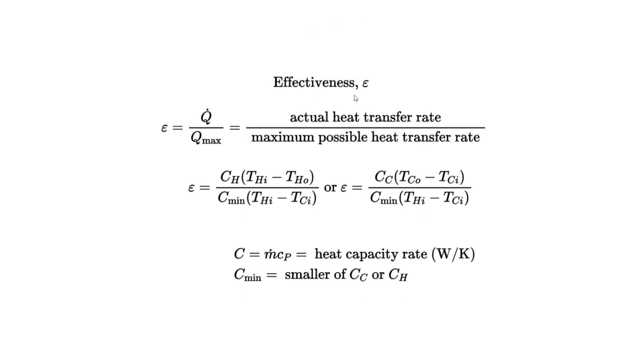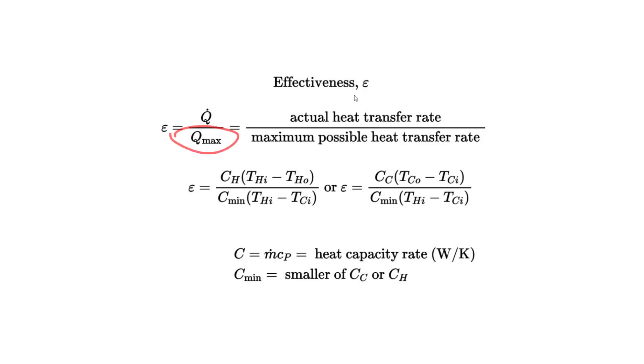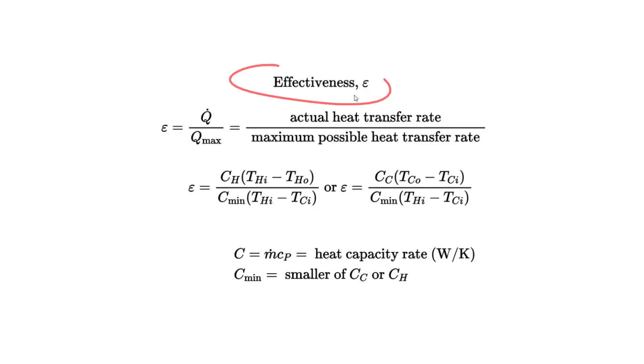The last thing to mention is the effectiveness ratio: ε = Q dot actual / Q dot max, the maximum possible heat transfer. The effectiveness ratio tells us how close we are to the maximum possible heat transfer rate. If we know ε and Q dot max, we can determine the actual heat transfer rate. This is in the handbook and can also be evaluated using additional equations.